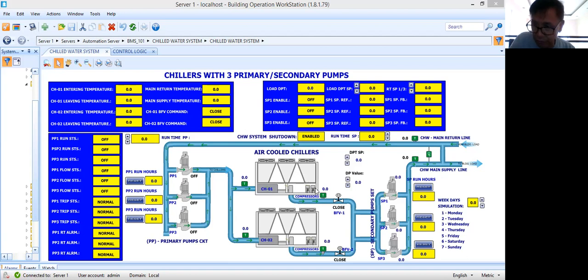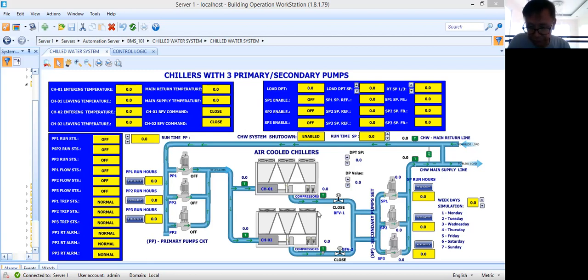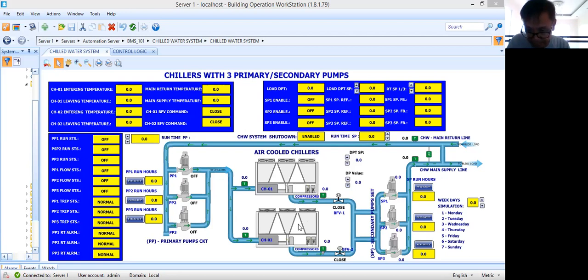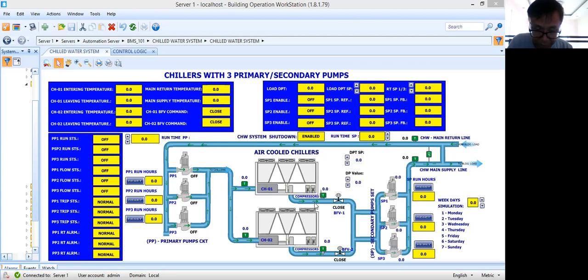Each chiller will have two compressors. Now for the staging of these compressors, the chillers — chiller one and chiller two — they have their own microprocessor-based controller. Their own controller will be the one to stage the compressors based on the load. So that will not be our scope in the control logic programming.